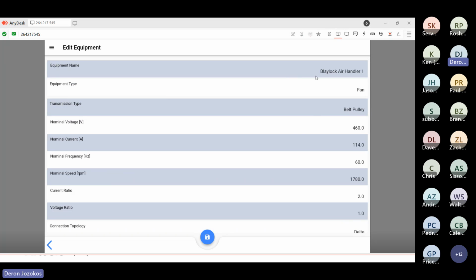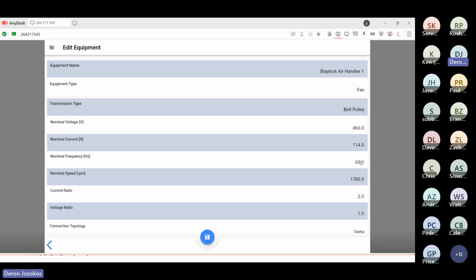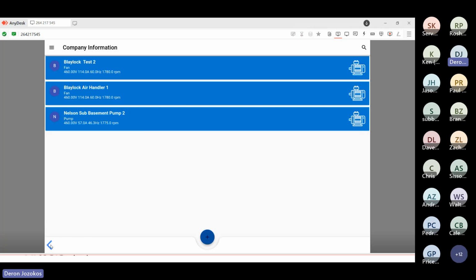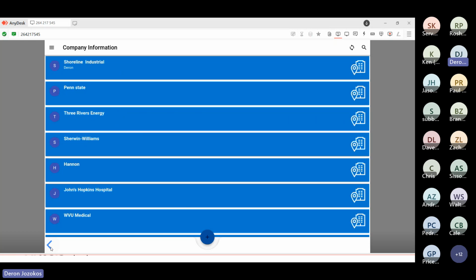Equipment name, enter the name, whatever nomenclature you use there. Is it a fan? All these different types of machinery, belt or pulley driven, nominal voltage, nominal current, nominal frequency, 60 hertz, full load running speed. The current ratios, that's just the CT ratios that we're using for this particular asset. And then the voltage ratio, connection topology. Once you enter in the motor nameplate information, you click Save. Now you just built a full asset. You're ready to take a measurement.